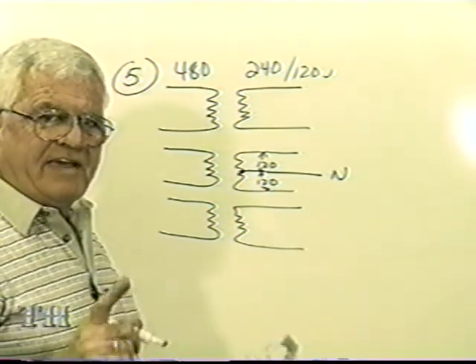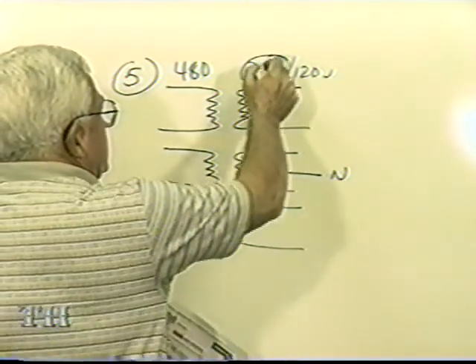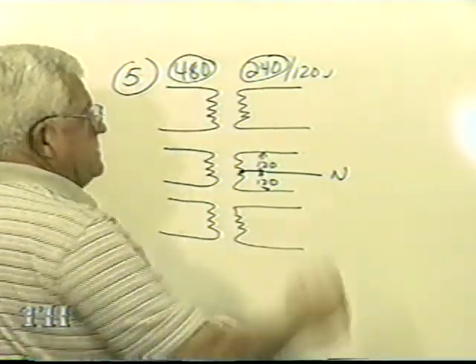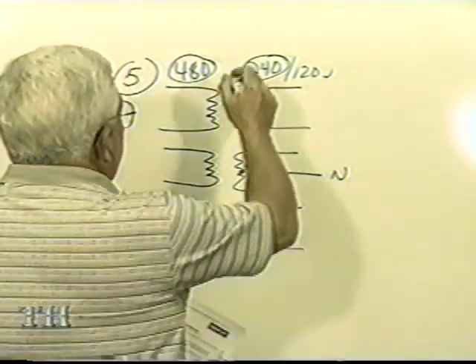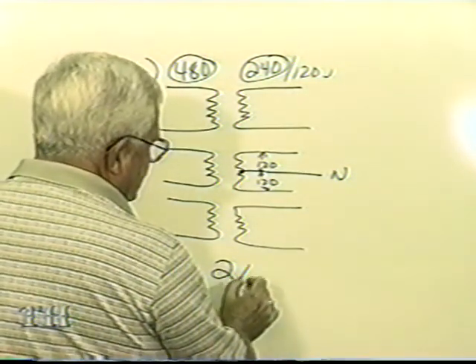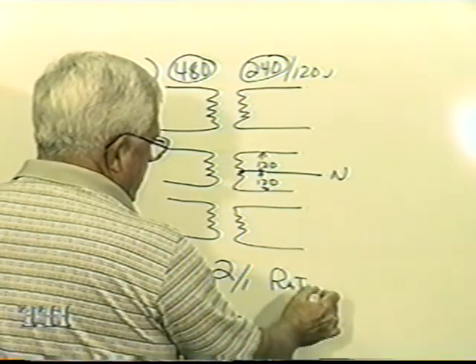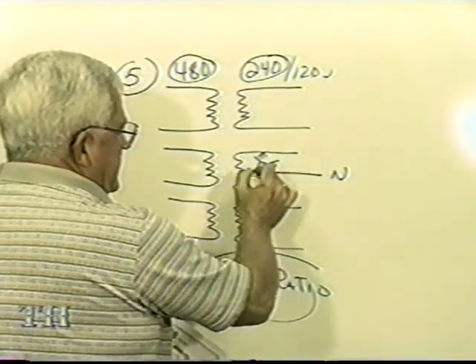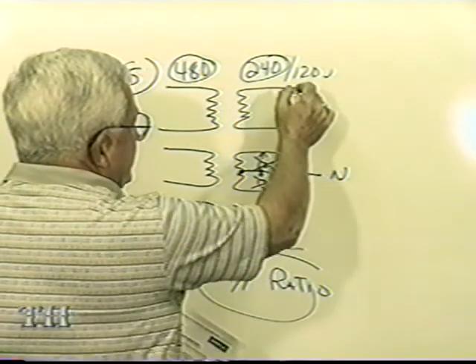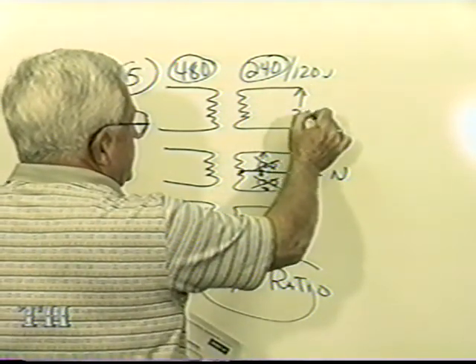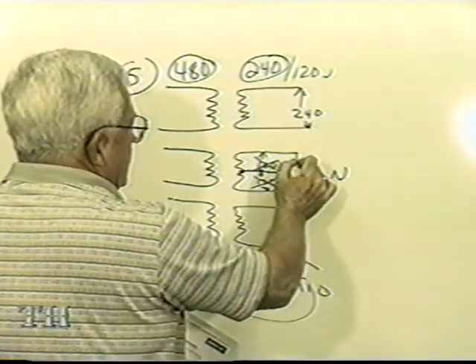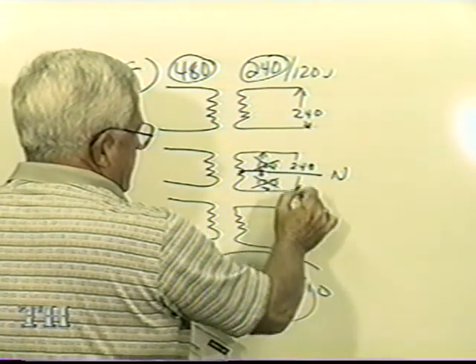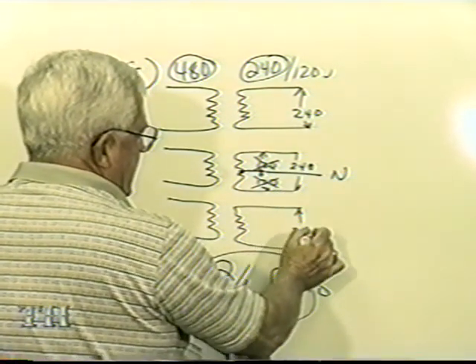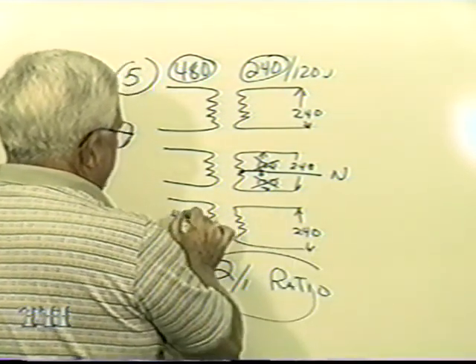But what's the phase voltage? 240. Phase voltage, remember? You're going to come back with a correct answer of a 2-to-1 ratio. The 120 is not a phase voltage. Your phase voltage is 240 volts on all of this. And your phase voltage over here is 480.